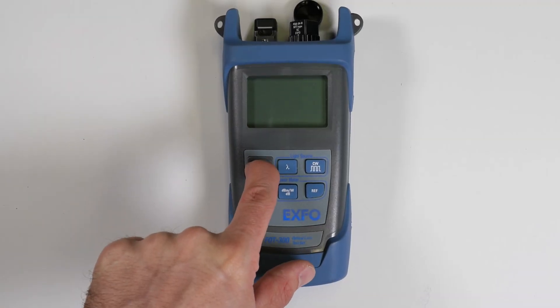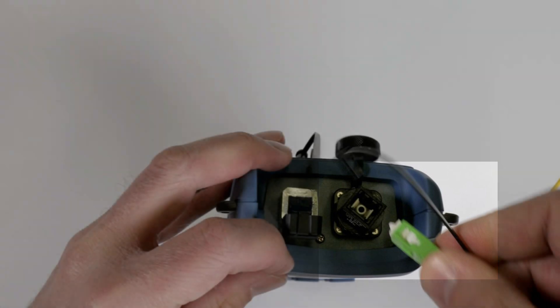Press the power button to turn it on. Inspect the fiber ends with a fiber inspection probe and clean if needed. Connect the fiber to the power meter of the FOT300 using the appropriate adapters.